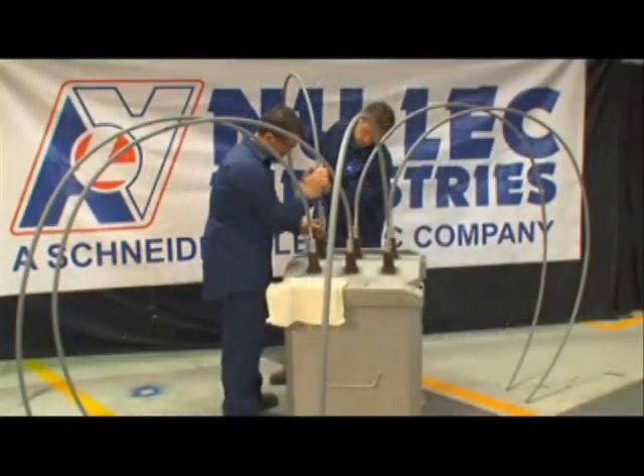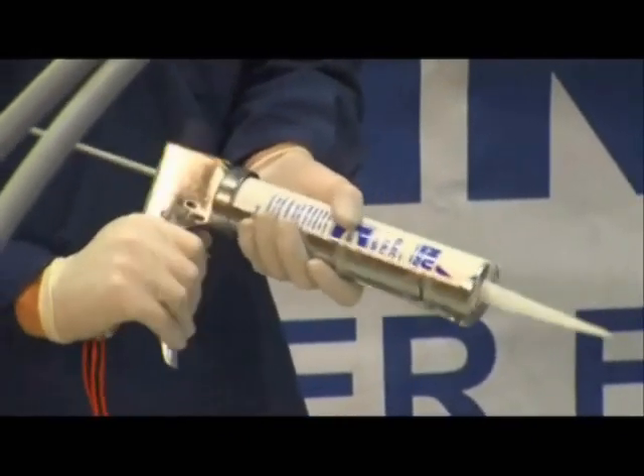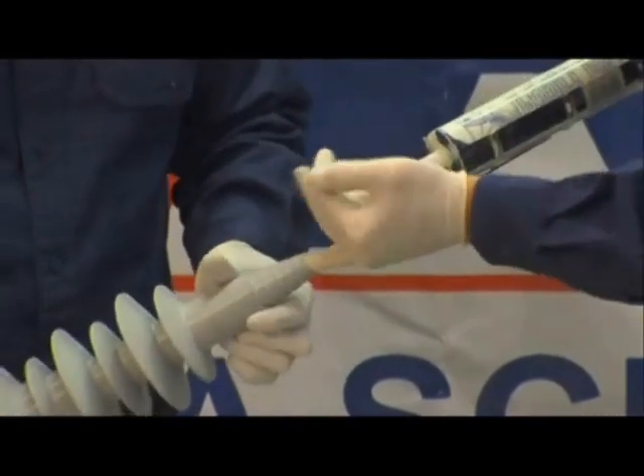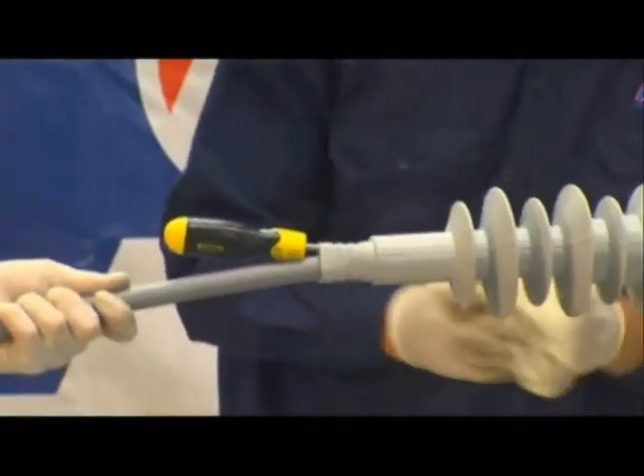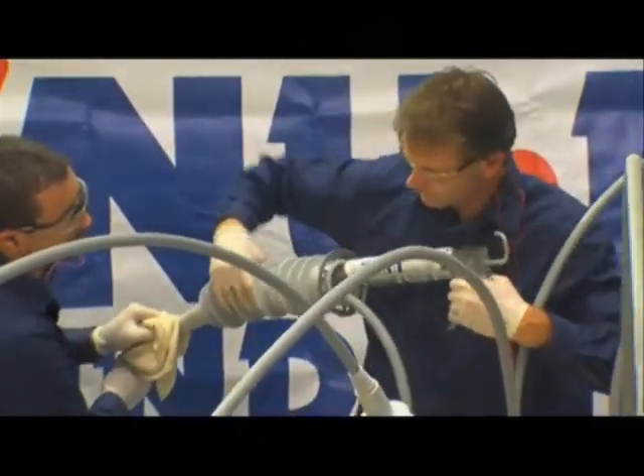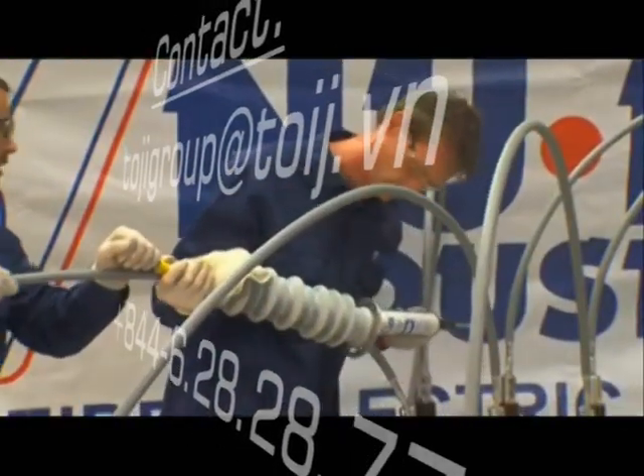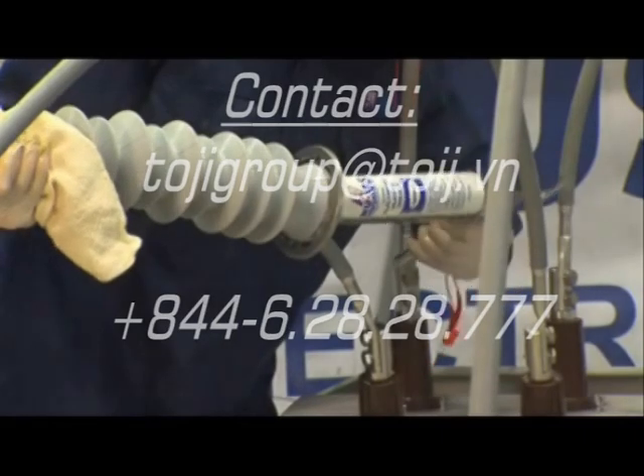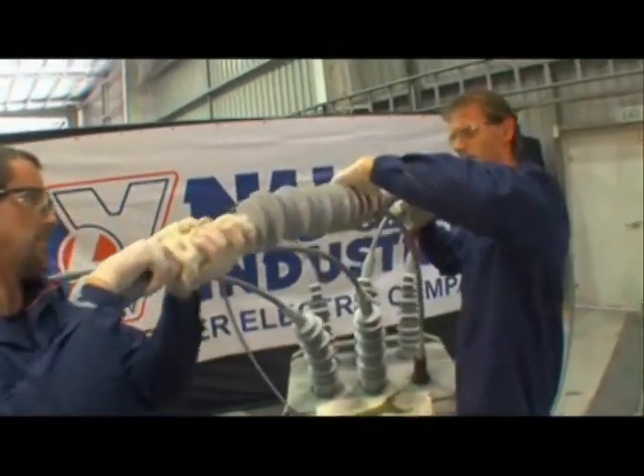It is important that both the flat washer and spring washer are used to avoid the possibility of the bolts loosening. Each bolt should be torqued to 44 Newton meters. To install the bushing boots, firstly charge the caulking gun with a tube of silicone paste and lightly grease inside the tapered end of the first bushing boot. Thread the cable through the bushing boot and slide it down the cable, stopping approximately one meter from the bushing. Place the screwdriver between the cable and the top of the boot to relieve air pockets that may be generated while the boot is being filled with paste.